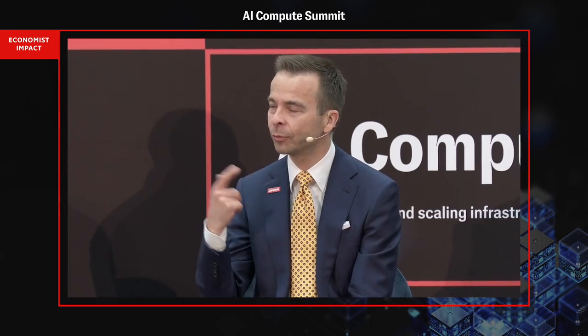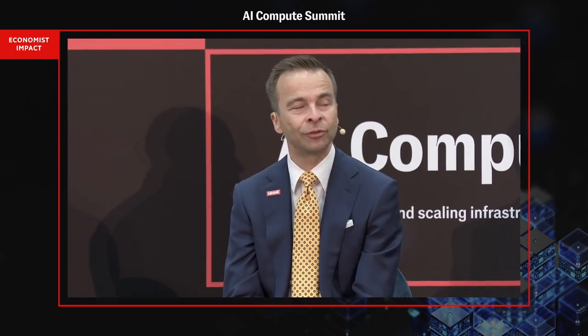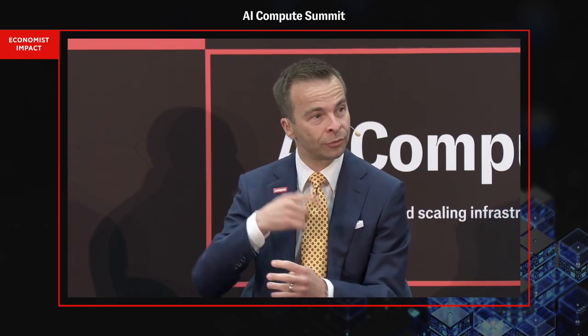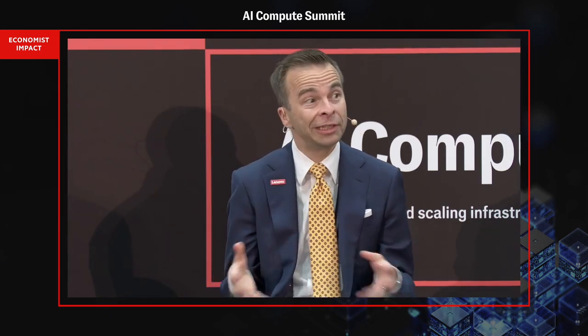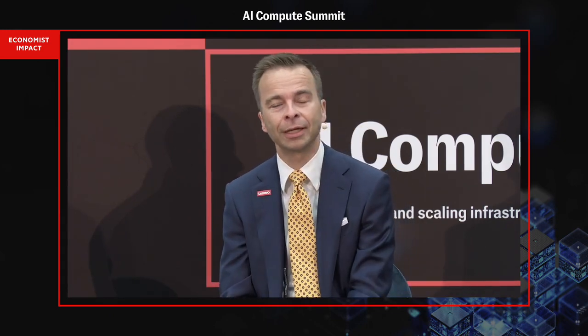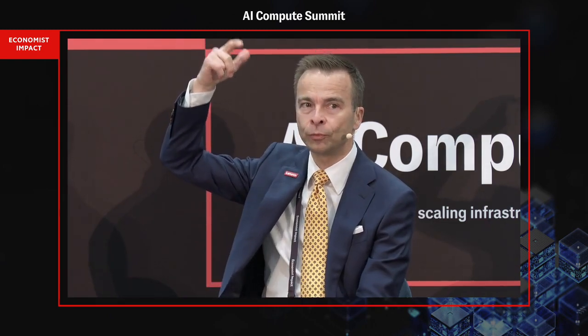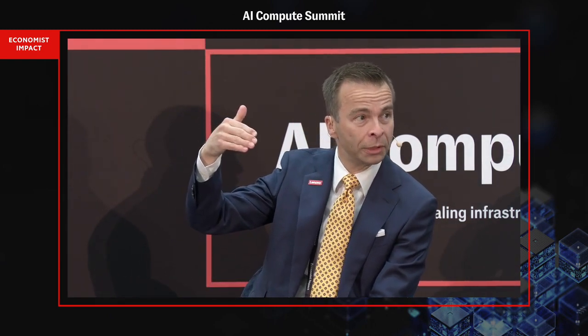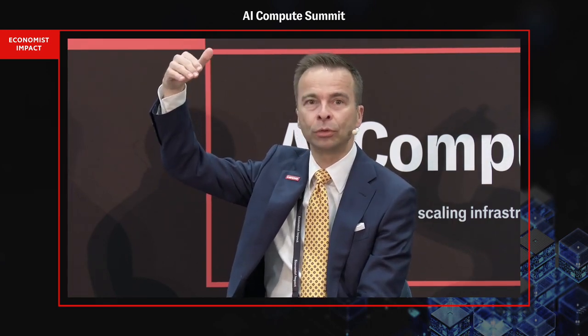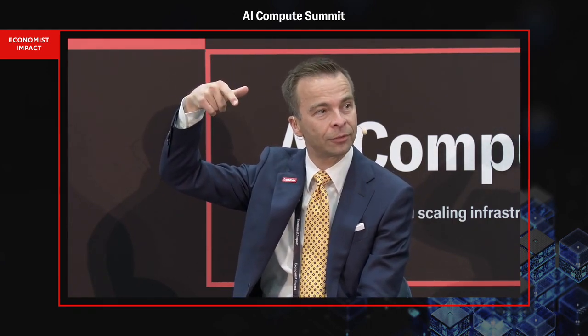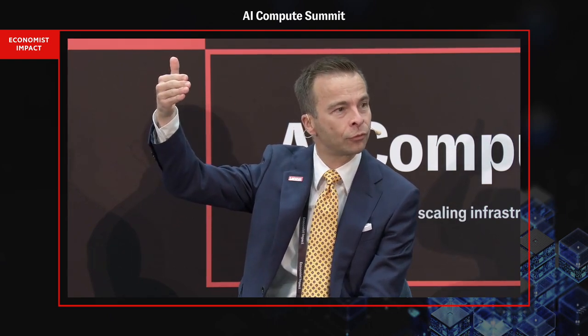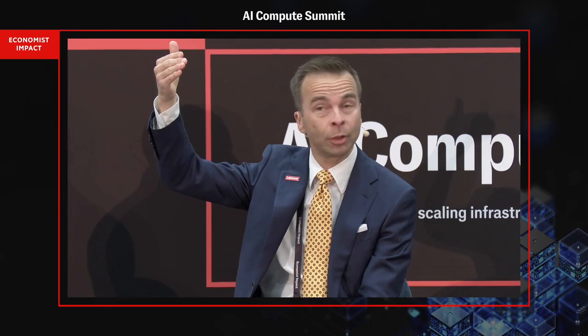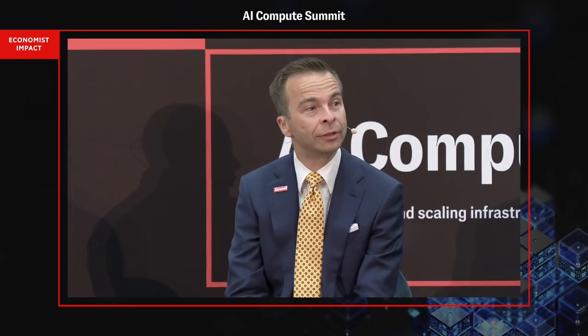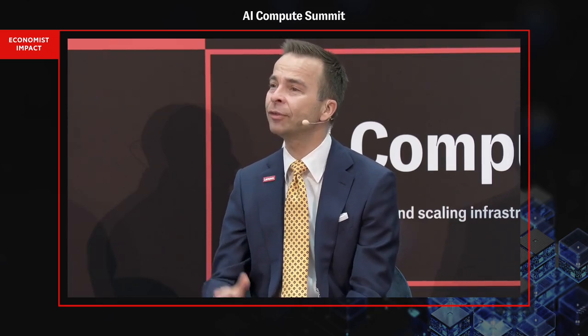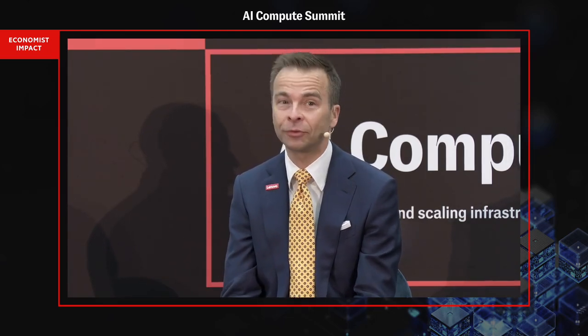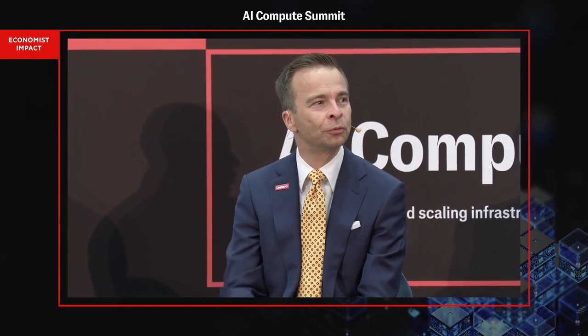The way we design the systems with closed loops, there is basically no water usage for that. You fill the pipes within the server system connected to the facility, and because there's no water leaking, you don't need to put more water in once it's in there. Even on the facility side, if you move it up to the roof, if you use high water temperatures - that's why we call it warm water cooling - you don't even need hybrid coolers on the roof to cool it down again. You can stay within that. You have 45 degrees into the server, 55 out of the server, and 55 you can typically still cool down in most places in Europe, especially Scandinavia, even with free cooling. So there's no water usage there. I know it's done differently in some places in the US, and that's where some of the misconception comes from. But maybe one tick in the mark on what Europe does differently there.